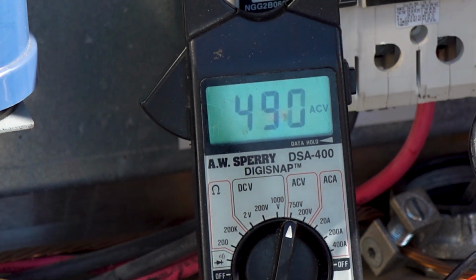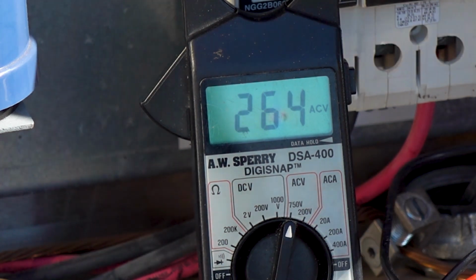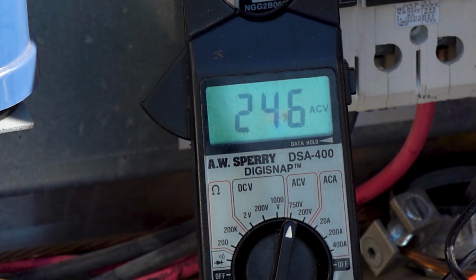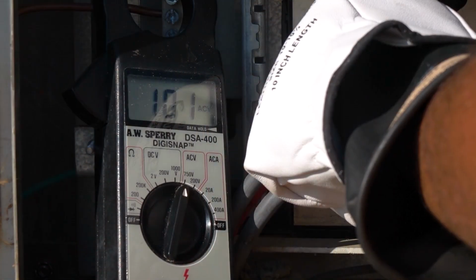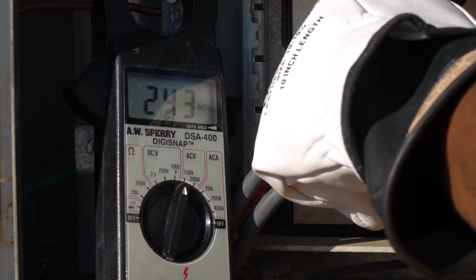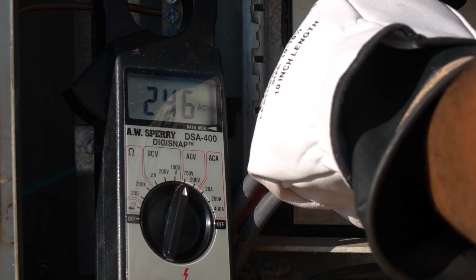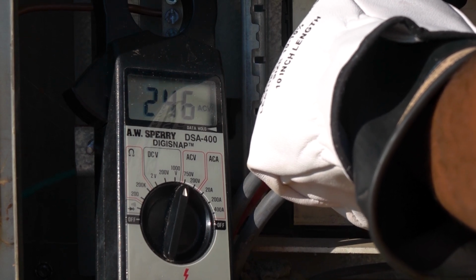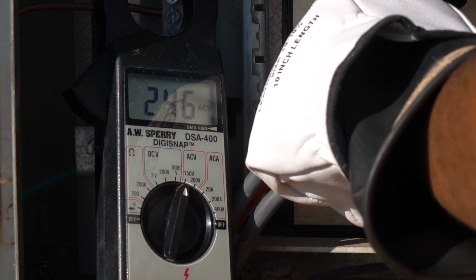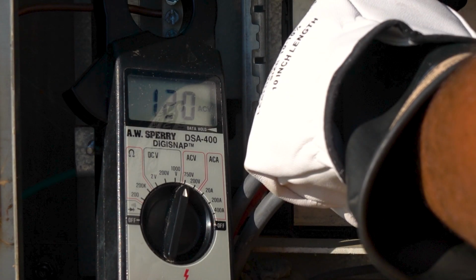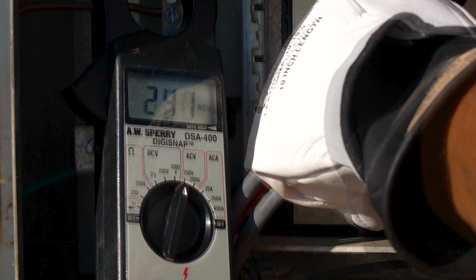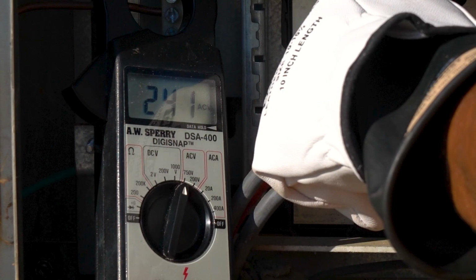On a 480-volt service, when measuring voltage between one of the energized conductors and ground, the inspector should see approximately 240 volts, which is 1/2 of the 480 volts, allowing plus or minus 5%. On a 120-240-volt service, line to line is 240 volts. When measuring voltage from one of the lines to neutral, the inspector should see approximately 120 volts, which is half of 240 volts, allowing plus or minus 5%.